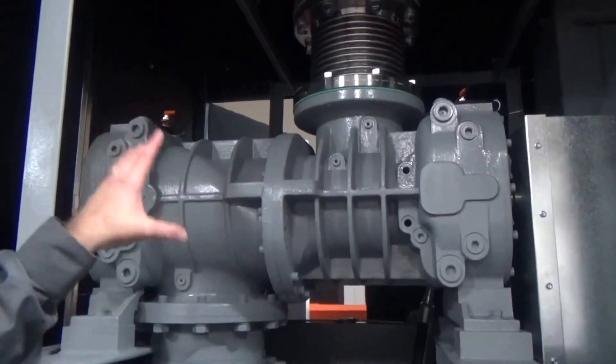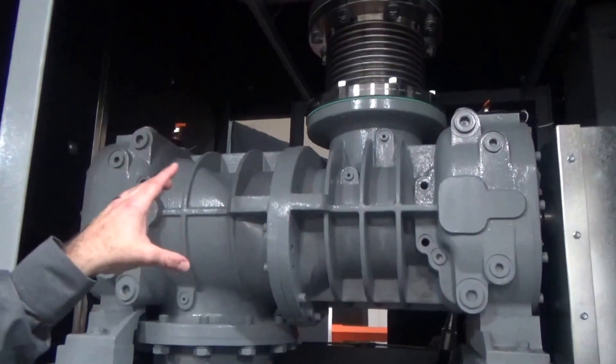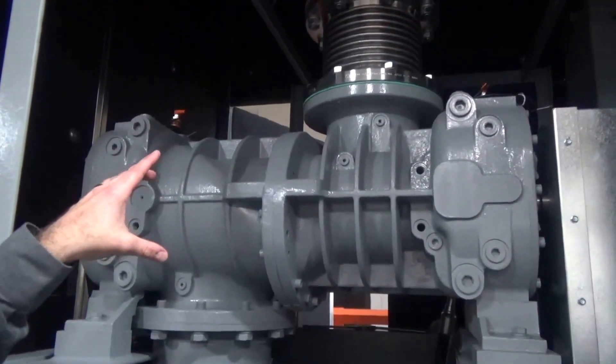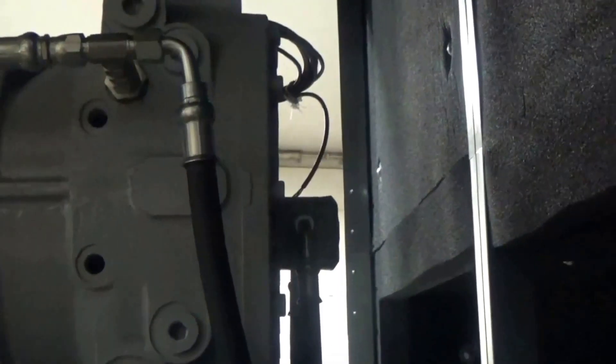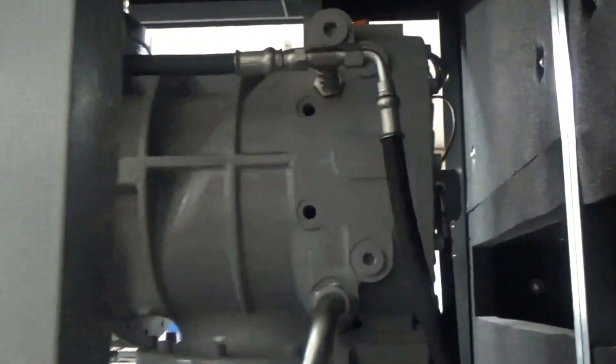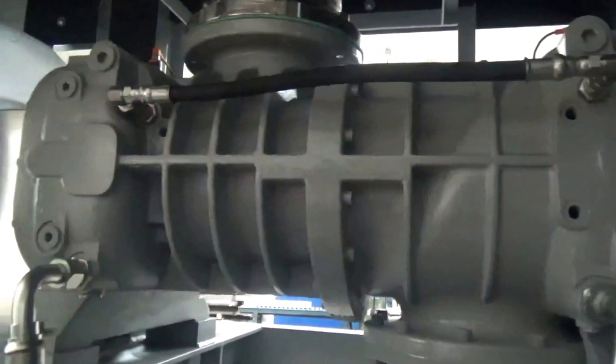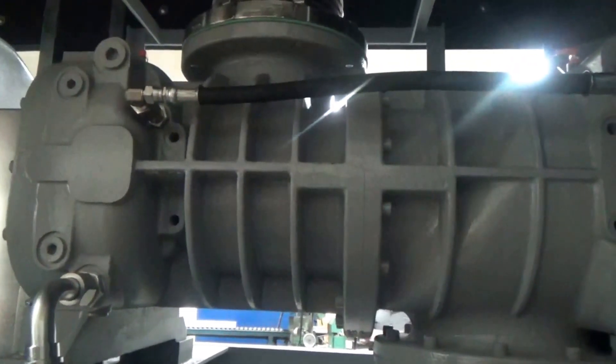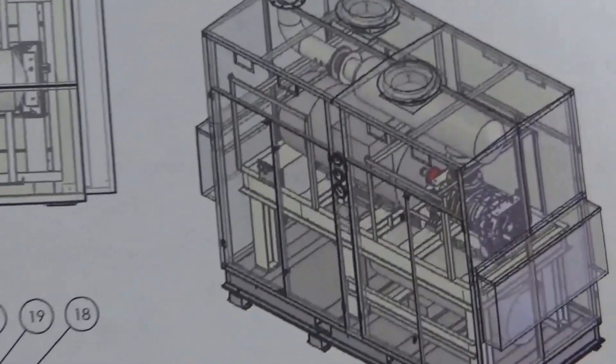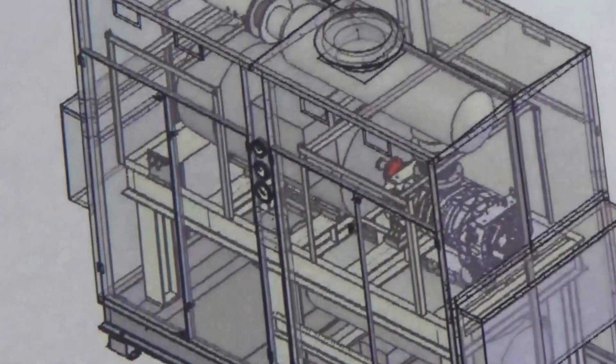This is the new Gardner Denver RC3 high pressure blower. Normal blowers are only rated up to 19 to 20 psi. This blower will go up to 36 psi. This will have a lot more opportunities for more dense conveying applications, usually where a compressor would have to be used. Now we can look at using a high pressure blower.